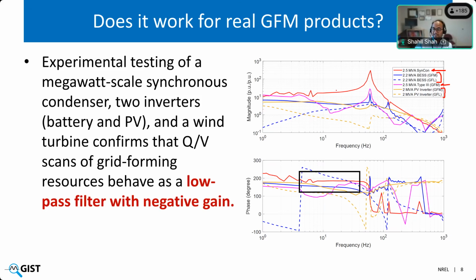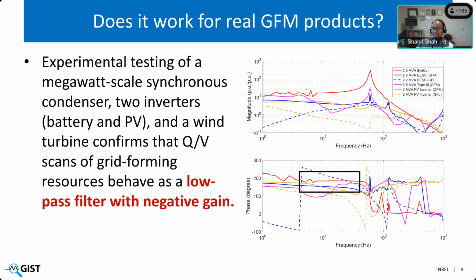These are all experimental results. The solid lines show the response of these devices when they are operating in grid forming mode, or with grid forming controls, I should say. The dashed lines are the response when the grid forming control is not activated. And clearly we see that the gain within this subsynchronous frequency range has that behavior of voltage source behind reactor, more so for the synchronous condenser. For the synchronous condenser, you really see this second-order low pass filter with very low damping at the fundamental frequency and then the gain rolling off, and the phase also stays around 180 degrees. So the commercial products do satisfy this behavior for grid forming resources.